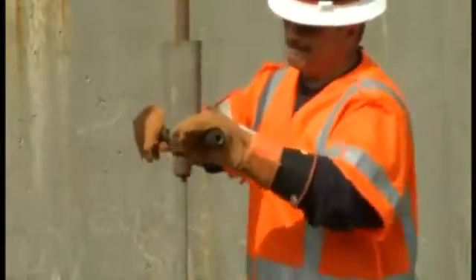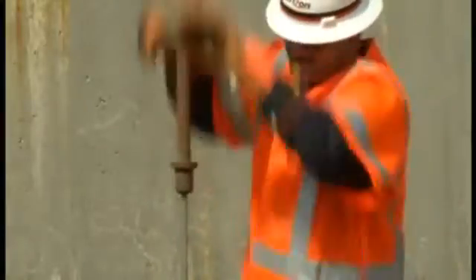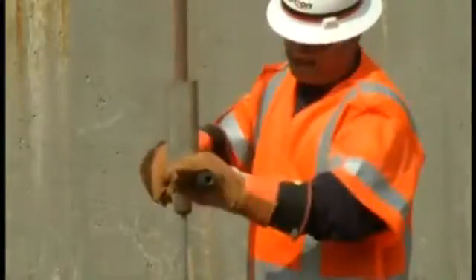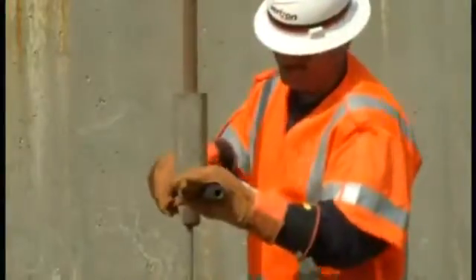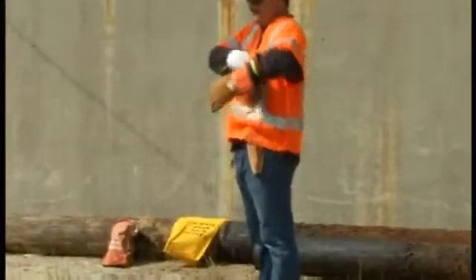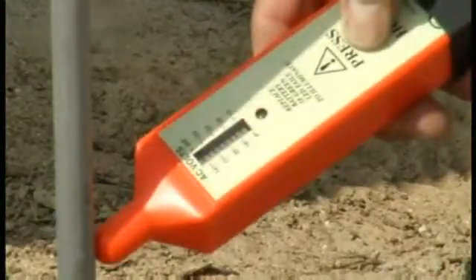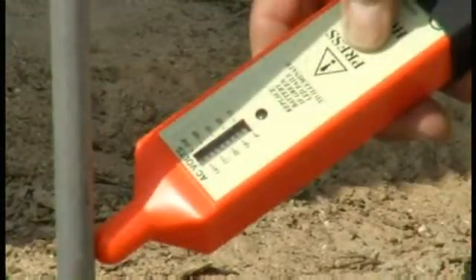Driving a ground rod. Buried electric can be a hazard when driving a ground rod. Insulating gloves are to be worn while driving the ground rod. Once the ground rod has been driven to its proper depth, the insulating gloves are to be removed, and the ground rod tested with a voltage detector before proceeding.